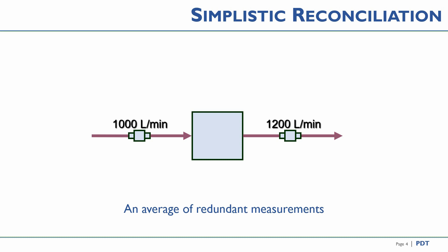Dynamic data reconciliation is the concept of using many measurements from the process and validating them against each other. We want to eliminate faulty measurements and correct for bias in the data. We want to turn noisy and erroneous process data into actionable knowledge. This data reconciliation becomes the foundation of a successful implementation of a process digital twin.